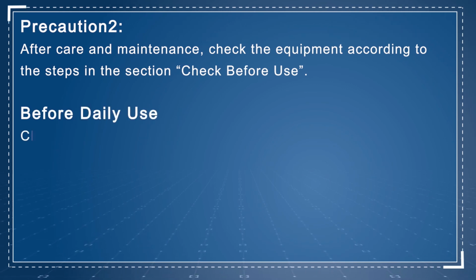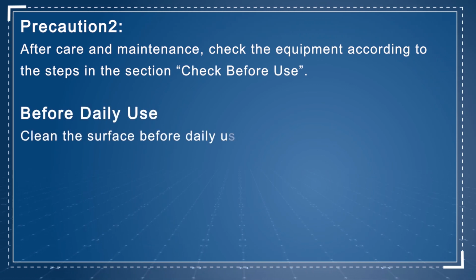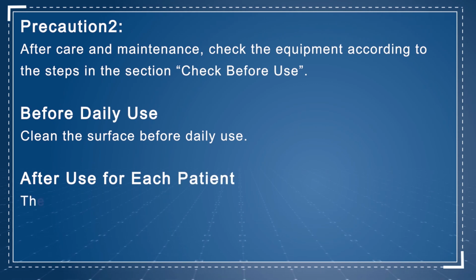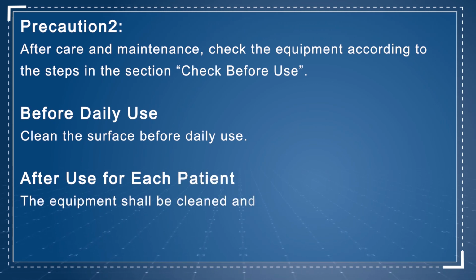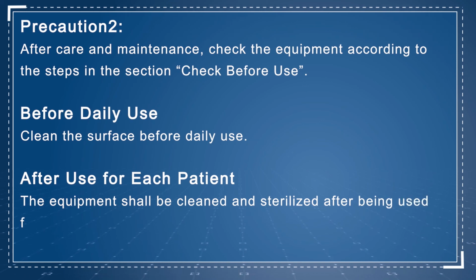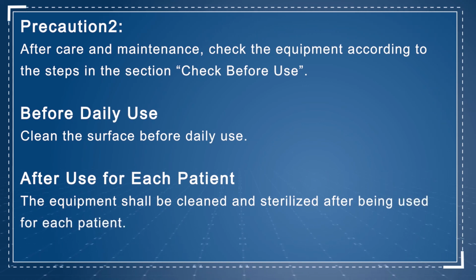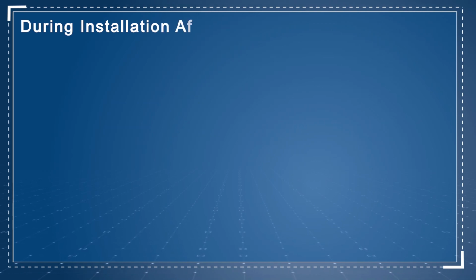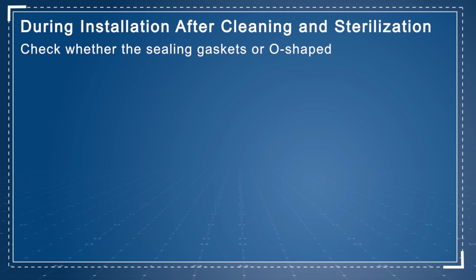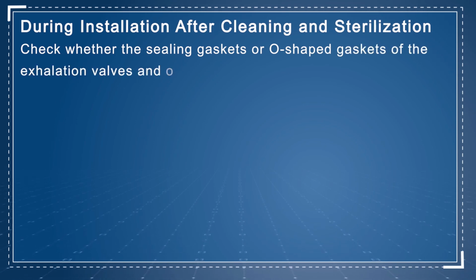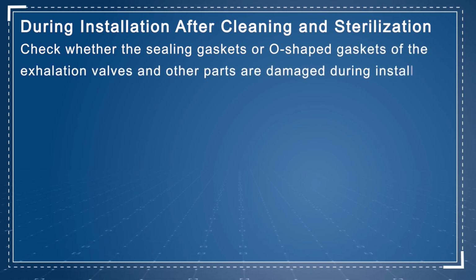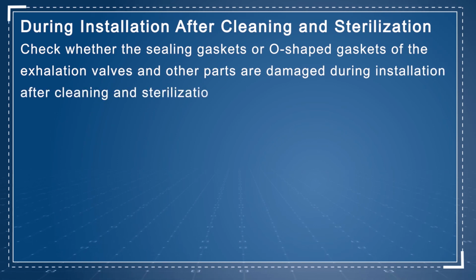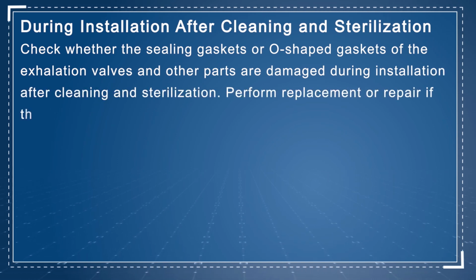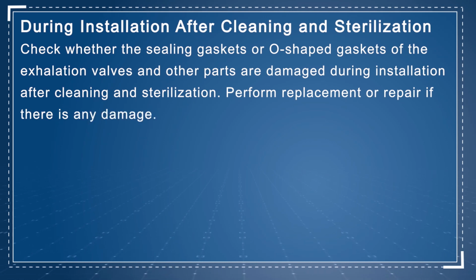Check before use. Before daily use, clean the surface. After use, the equipment shall be cleaned and sterilized after being used for each patient. During installation after cleaning and sterilization, check whether the sealing gaskets or O-shaped gaskets of the exhalation valves and other parts are damaged. Perform replacement or repair if there is any damage.